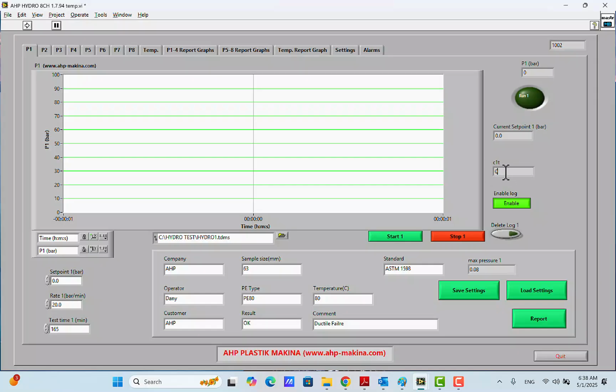This is an important function for protecting the pump in case of any disconnection of the water in the main water supply line, or any case of leakage or burst of the sample in the downstream. Suppose a sample starts leaking or suddenly bursts, and the pressure will drop here, and the controller starts pumping to get to the set pressure, but the pressure is not getting to the set pressure because you have a burst sample or leaking or anything that caused it. If this protection is not activated, of course, the pump will be working continuously till failure of the seals and seal seats inside the cylinder of the pump.